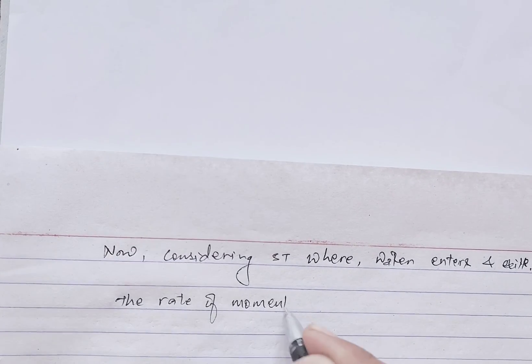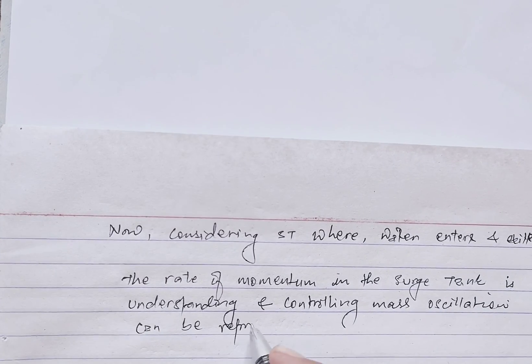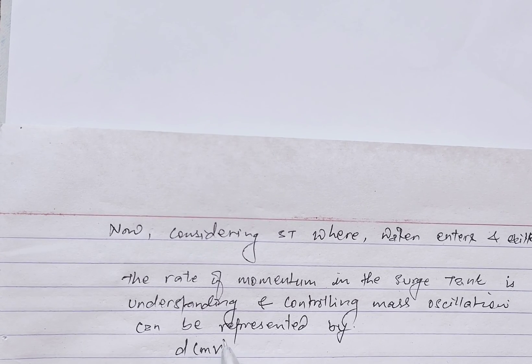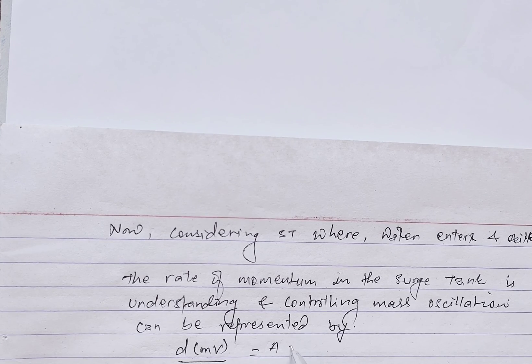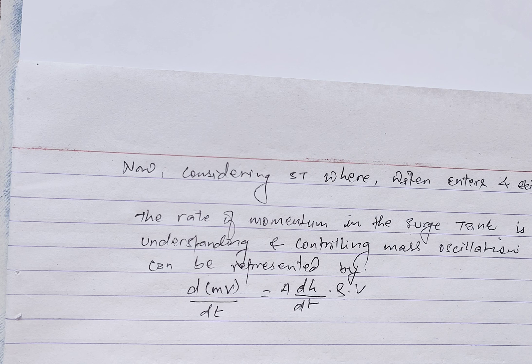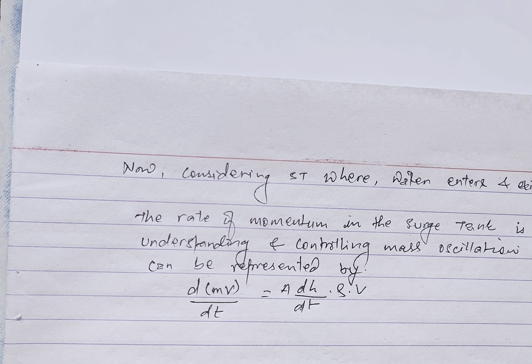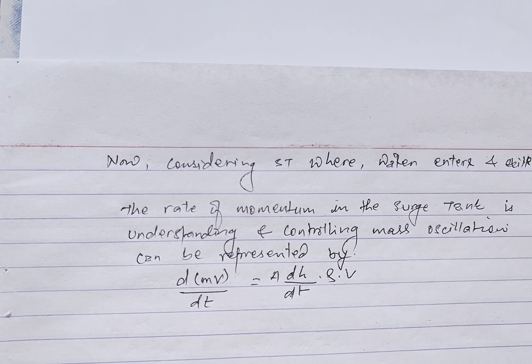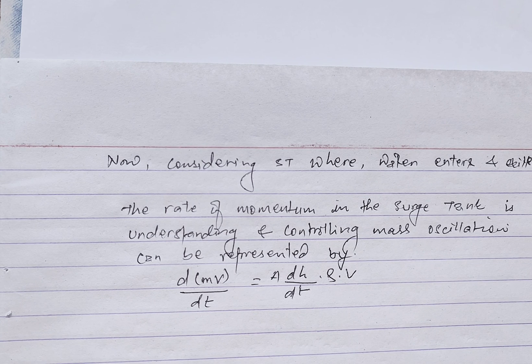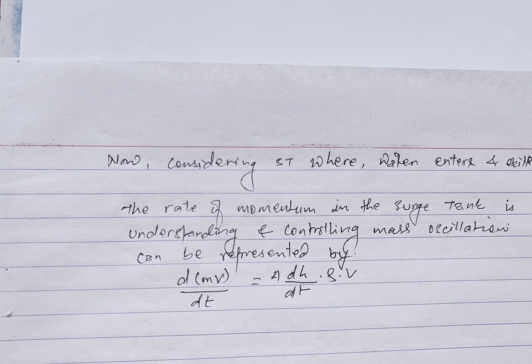Consider a surge tank where water enters and exits. The rate of change of momentum in the surge tank is critical in understanding and controlling mass oscillation: dm·v/dt = A · (dh/dt) · ρv, where m is the mass of fluid in the tank, v is the velocity of water, A is the cross-sectional area, and dh/dt is the rate of change in water height. To control mass oscillation, the focus is on designing the surge tank to minimize rapid changes in water height (dh/dt), achievable through appropriate surge tank volume, damping mechanisms, and control systems.